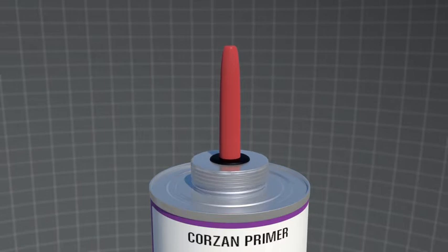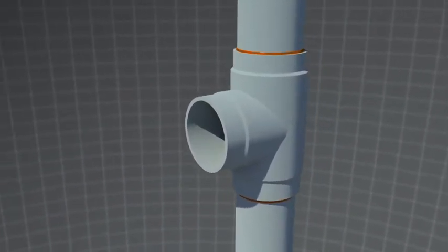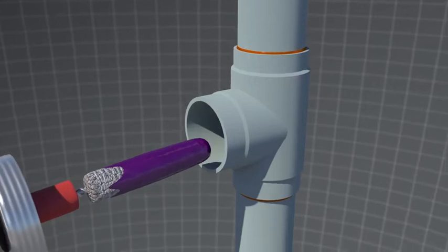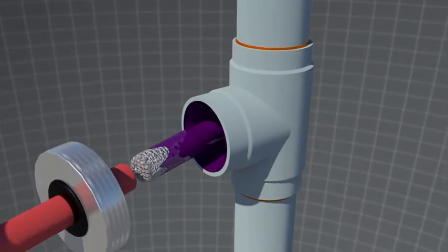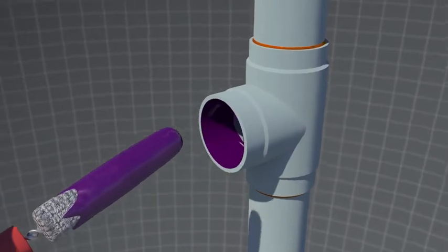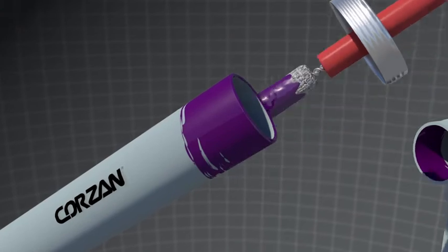With Corzan pipe and fittings, you must utilize a primer in the solvent weld process. Apply an even coat to the inside of the fitting. Use pressure to aggressively coat the surface and re-dip your dauber as needed. Then, apply an even coat of primer in the same manner to the outside surface of the pipe.